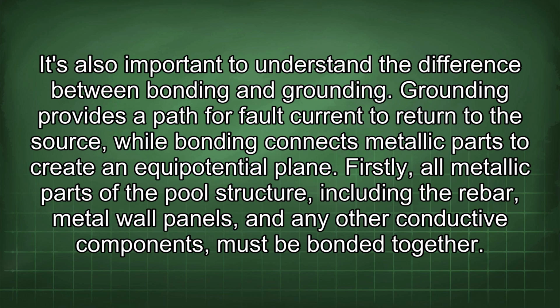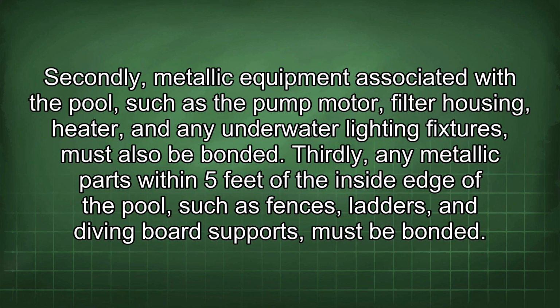equipotential plane. Firstly, all metallic parts of the pool structure, including the rebar, metal wall panels, and any other conductive components, must be bonded together. Secondly, metallic equipment associated with the pool, such as the pump motor, filter housing, heater, and any underwater lighting fixtures, must also be bonded. Thirdly, any metallic parts within 5 feet of the inside edge of the pool, such as fences, ladders, and diving board supports, must be bonded.